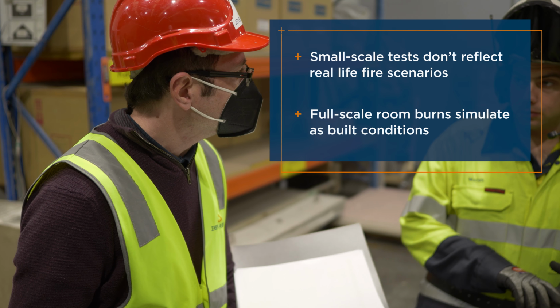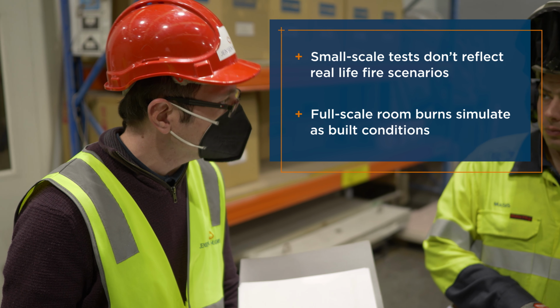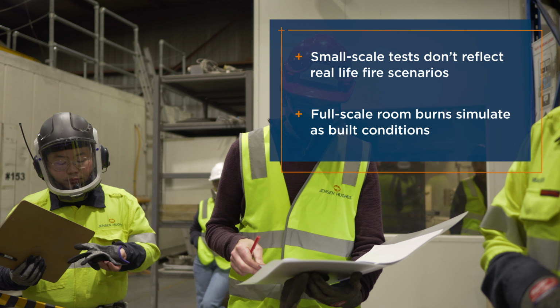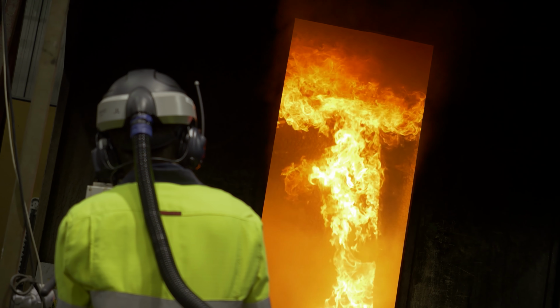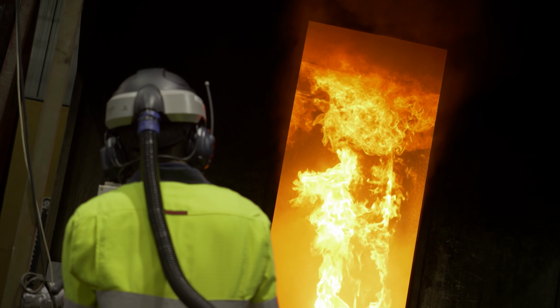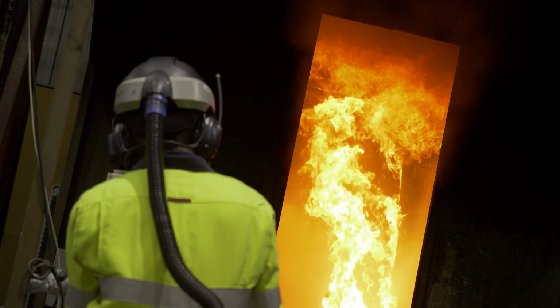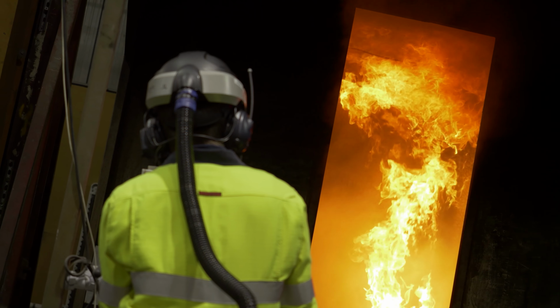Many materials intended for use as wall or ceiling linings are not suitable for evaluation using the small-scale oxygen consumption cone calorimeter test, due to the way in which they react to the heat source or the complexity of their composition. The Australian Building Code therefore references a full-scale test to AS/ISO 9705 to replicate as-built construction under controlled conditions.